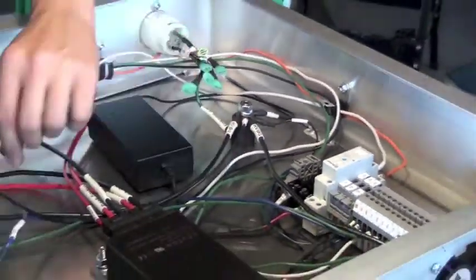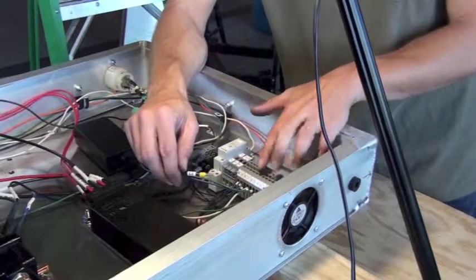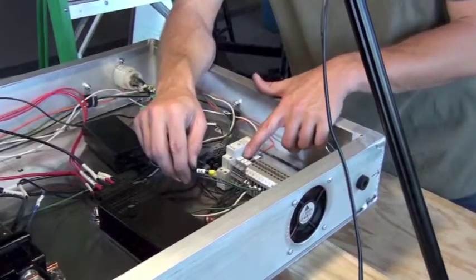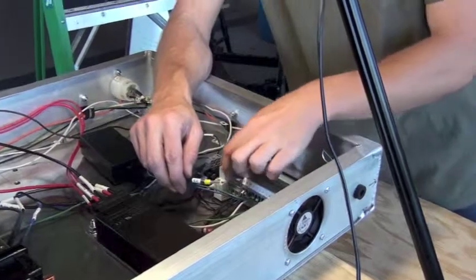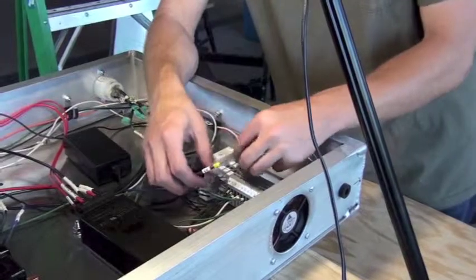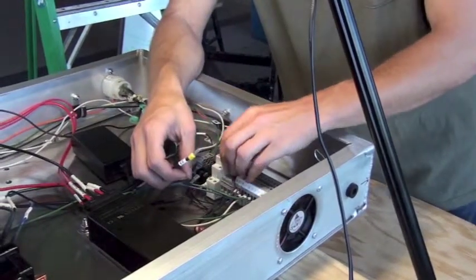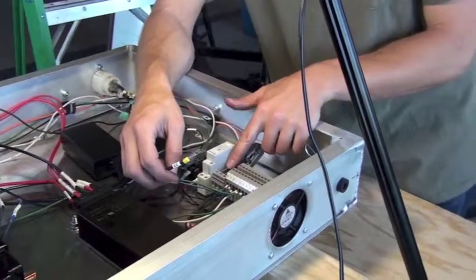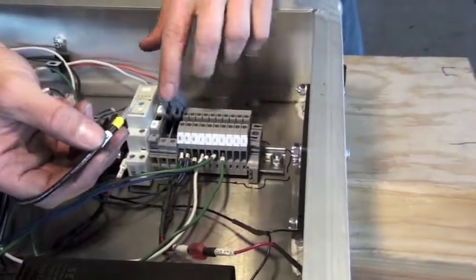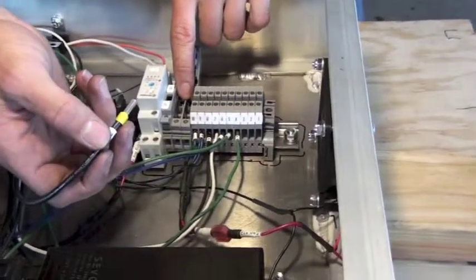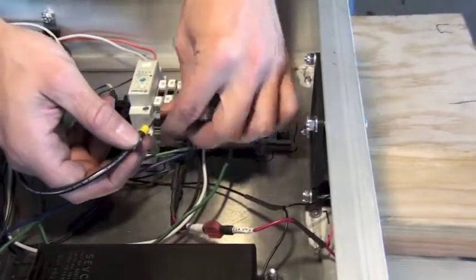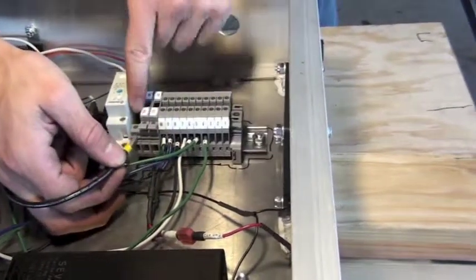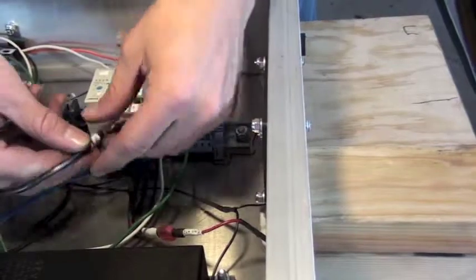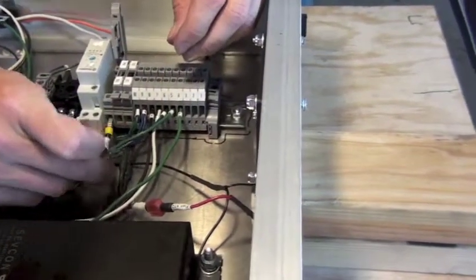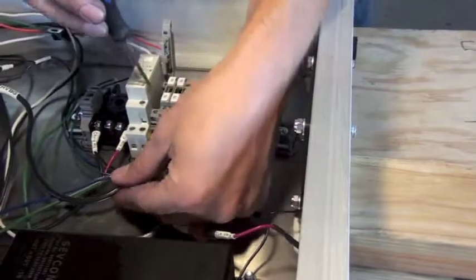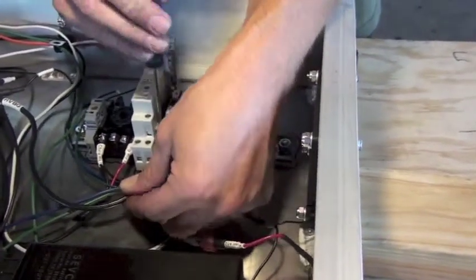Now let's take a look at the other end of these negative wires we've connected to the common ground. The one going to the DIN rail goes to a fused position, number 23 on the DIN rail. Notice that the smaller numbers 1 through 20 are just straight through connections. 21, 22, and 23, however, are fused connections. So if we pop open these 21, 22, and 23 spots on the DIN rail with the fuses, we can see how the fuses fit in. But you also need to pop it up to tighten the wire down. So you'll see the screw connection here. So insert your negative cable into spot number 23 and tighten it down into place. We'll add the fuses into the DIN rail at a later point in the assembly process.